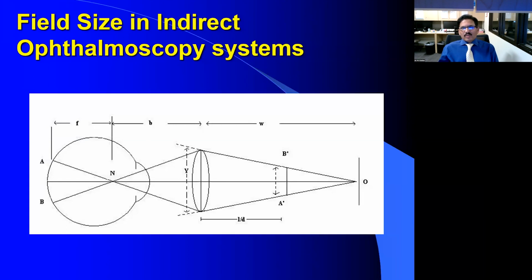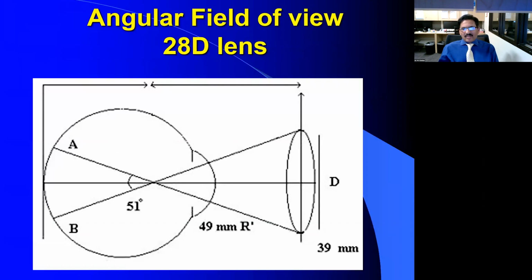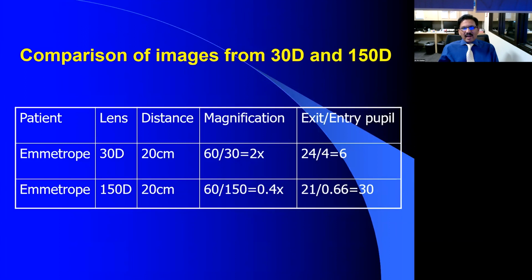But obviously, the lens was so big, we can't use it in the operating room. So we had to miniaturize it. And if you miniaturize, obviously, you can get a large area of retina that can be seen. So the calculation was optically, how much lens can you manufacture comfortably without distorting, because the weight of the lens can cause problems for the geometry of the eye. So the limitation was 150 diopter lens can be made. That's what Volk Optical told us. So we said, well, let's go for it. So the view obviously improves a lot, but you get a minified image. So how do you deal with that?